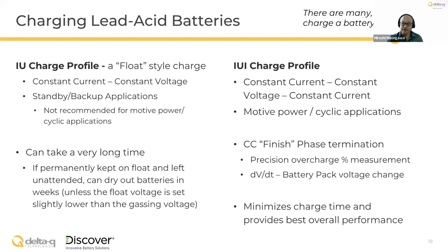If left unattended, one downside is that IU charging can dry out a battery over the course of weeks. One way to prevent and remedy this is to make sure you're using the correct amount of charge. For most motive applications, which are cyclical—meaning the battery is drained and charged over and over—we shorten the float phase by running constant current, constant voltage, and then calculating a certain amount of overcharge. This method is called IUI: constant current, constant voltage, then constant current. This minimizes charge time and provides the best overall performance.